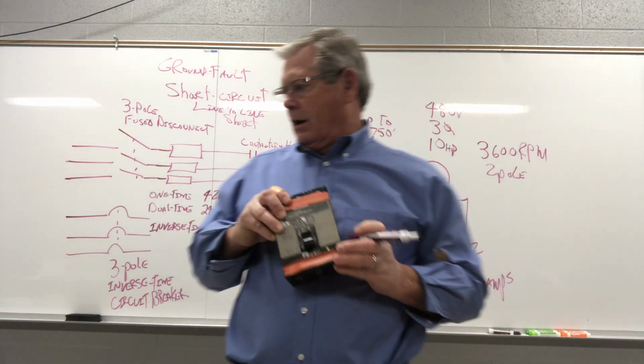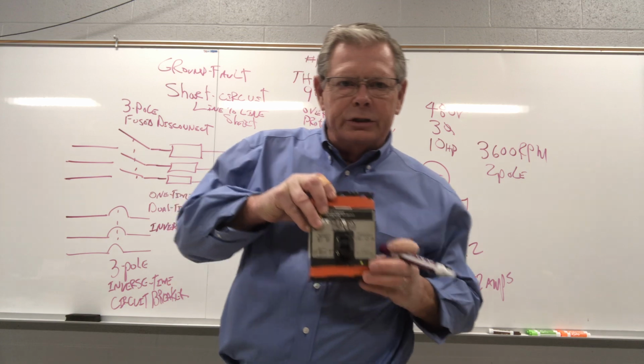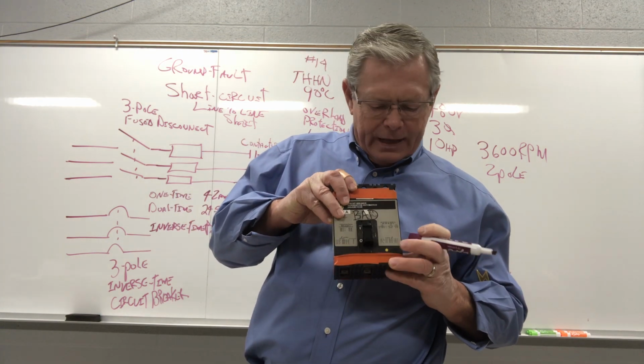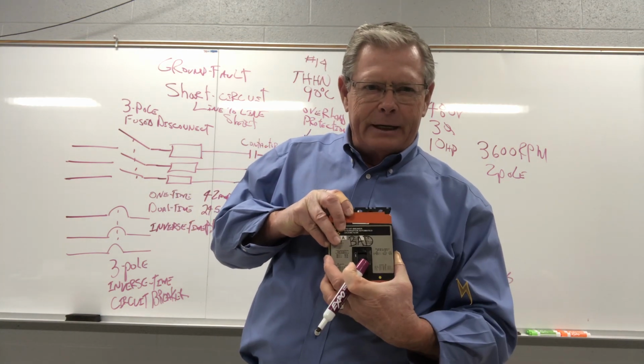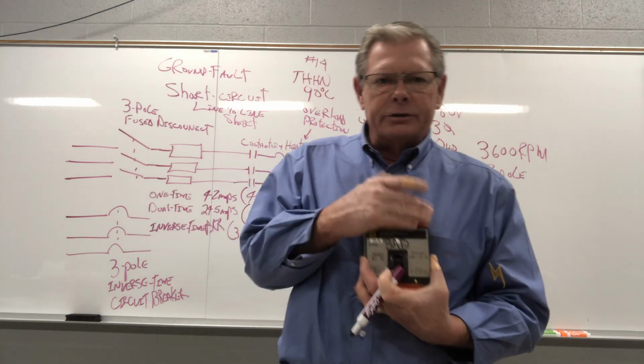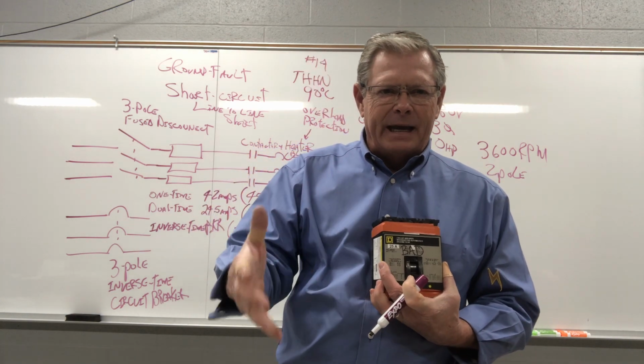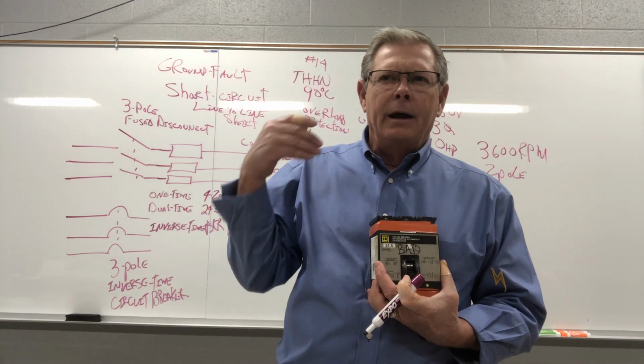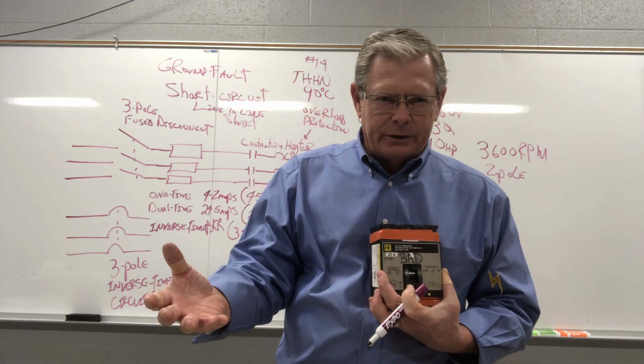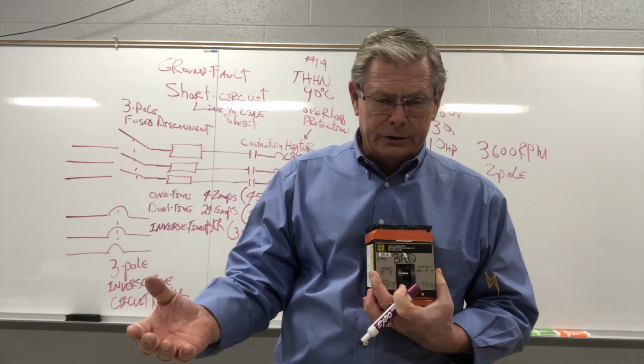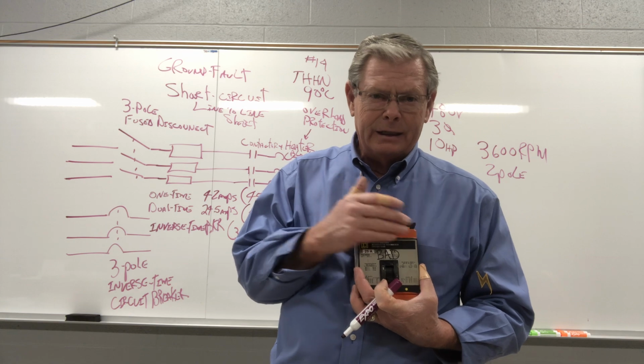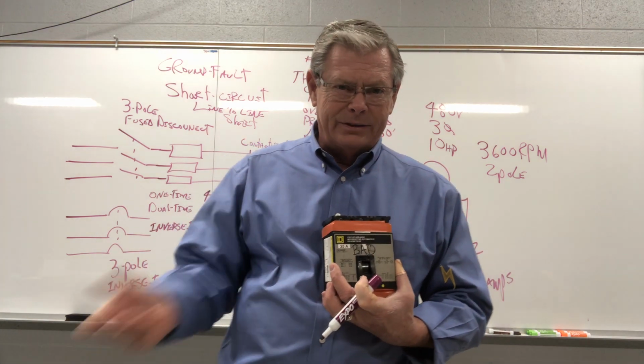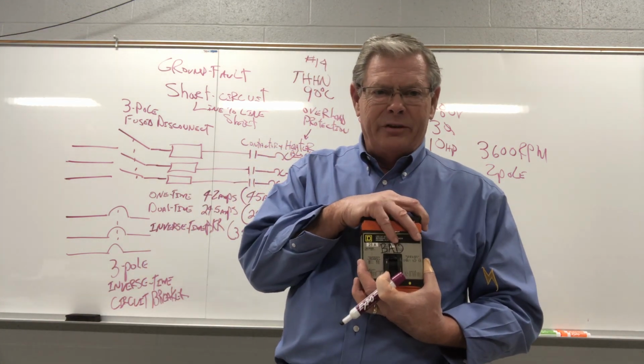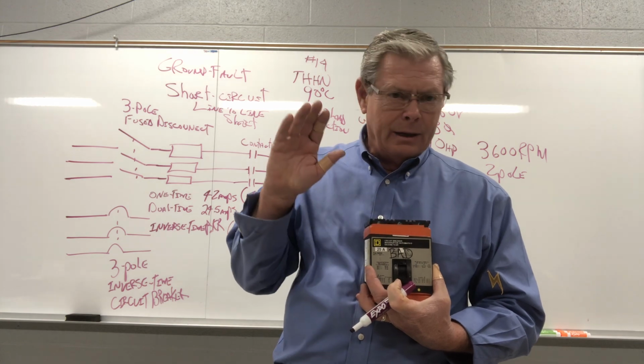Okay, if you have a breaker that has a little adjustment here, that little adjustment is a magnetic trip. Your regular circuit breaker is going to trip in 6 to 8 cycles. In time, 6 cycles on 60 hertz power distribution is 1/10 of a second. So 0.1 to 0.15 seconds is the time this thing's trying to heat up to trip.